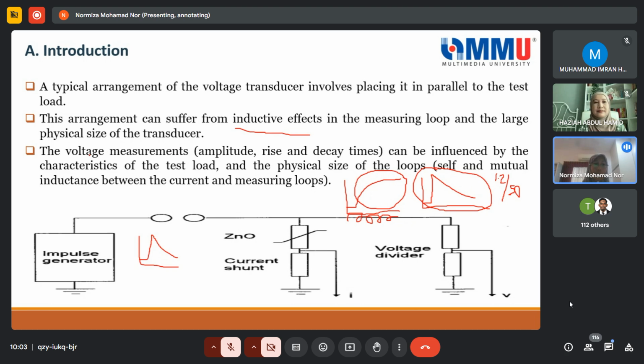Anyway, here, the voltage measurement, amplitude, rise and decay times are very much influenced by the characteristic of the test load. So if your test load is nonlinear, then you may have more delay. It may not be a problem if your test load is a linear load, because a linear load tends to have a similar characteristic. But if your test load is a capacitive load, like insulator, cable, transformer, the circuit representation is capacitive. So when combined with the inductance, now you have L and C in the circuit.